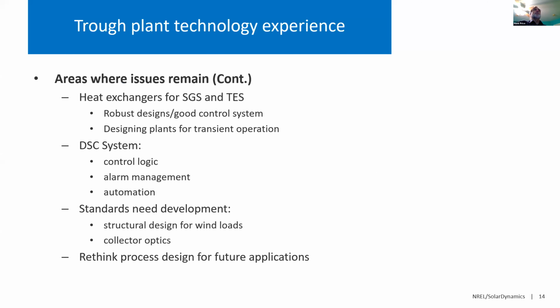As Mark mentioned, some of the bigger problems have been with conventional equipment. He mentioned heat exchangers, especially for the steam generation system and thermal energy storage systems. Those are systems that start up daily, so it's really important that you have robust designs for starting up the plant. He mentioned you need to design not just for the design point, the 100% case, but also for transient operation and especially starting up. This problem has occurred at a number of plants, not all plants, but it's really important to have good design that protects the heat exchangers during startup.